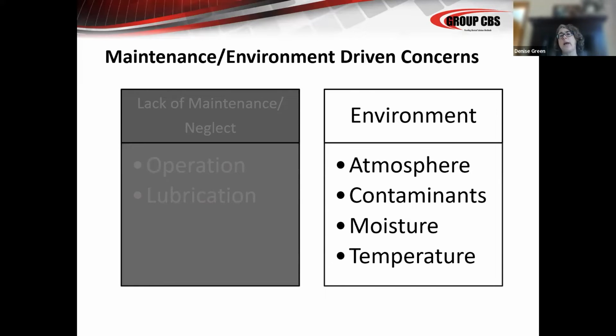The heater damaged the GPO3 to the extent that the voltage was able to jump from the pole piece to ground through that deteriorated GPO3. So that's a concern as well when you're working with environment and location. And then temperature is the last one.